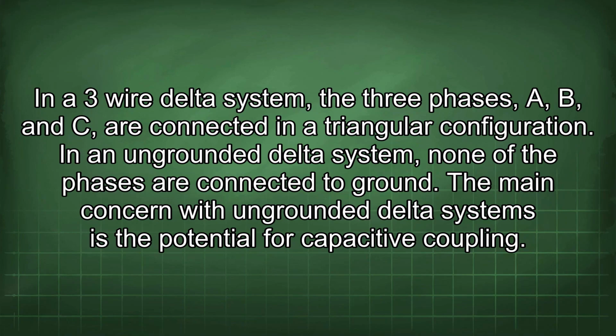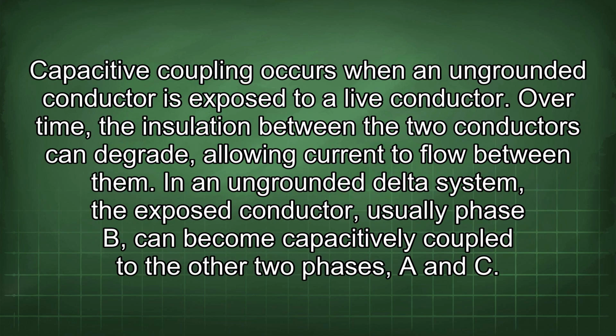In a three-wire delta system, the three phases A, B, and C are connected in a triangular configuration. In an ungrounded delta system, none of the phases are connected to ground. The main concern with ungrounded delta systems is the potential for capacitive coupling. Capacitive coupling occurs when an ungrounded conductor is exposed to a live conductor. Over time, the insulation between the two conductors can degrade, allowing current to flow between them.